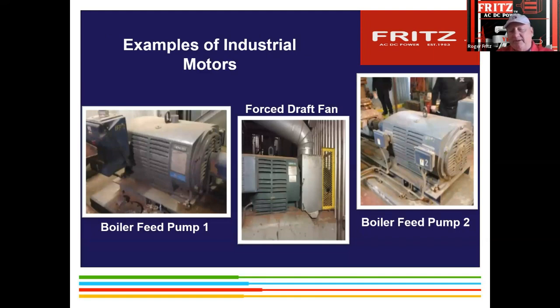These are some examples. These were medium voltage motors put in a power plant, about 750 horsepower. We put drives on the draft fans in the middle there, and we put them on both boiler feed pump one and pump two, which feed the boiler water into the boilers so that they could control that. There was a 10% service factor that they had to build in so they could never go over that. Well, by regulating the speed up to about 62, 63 Hertz, they got the extra amount of water that they could really use at the boiler. And it actually increased the output of the plant by almost another half a megawatt. That simple adjustment did it.